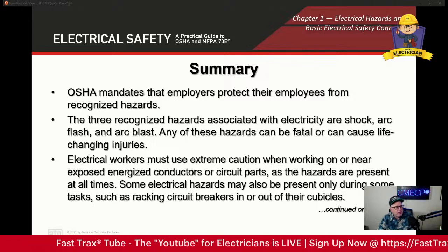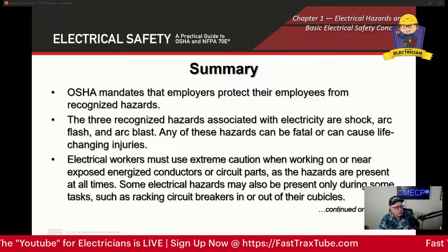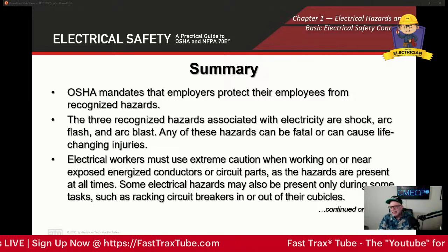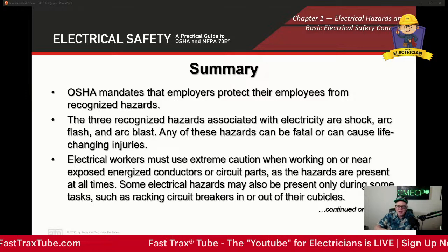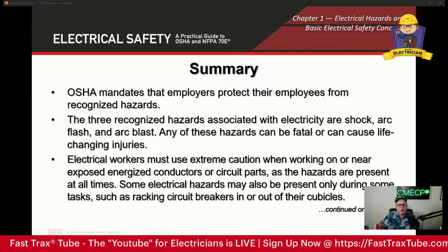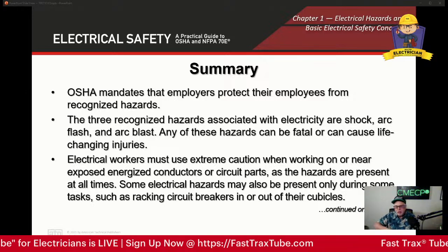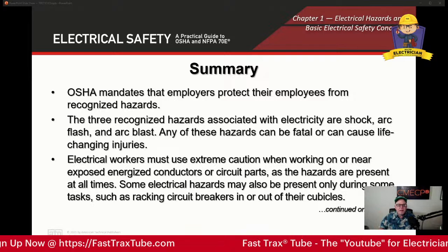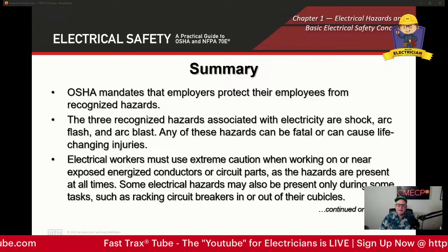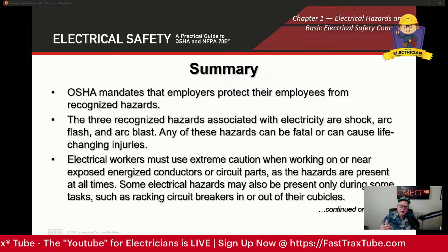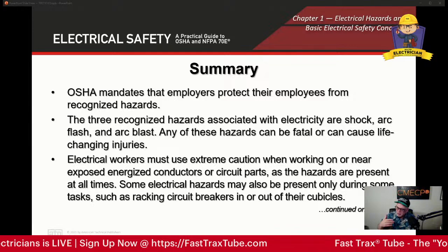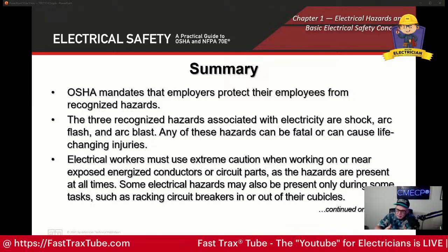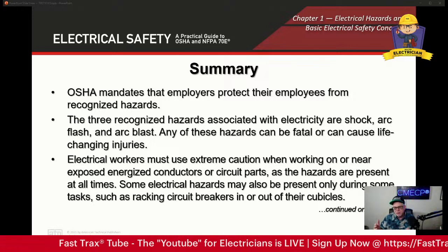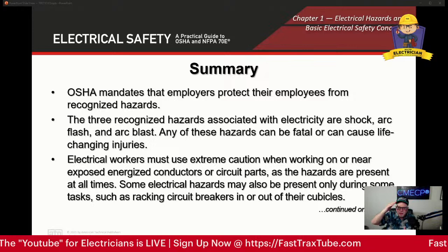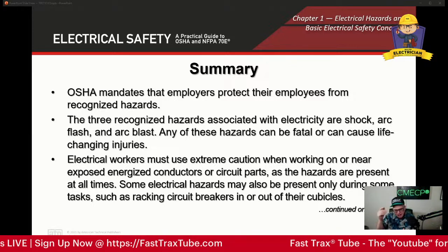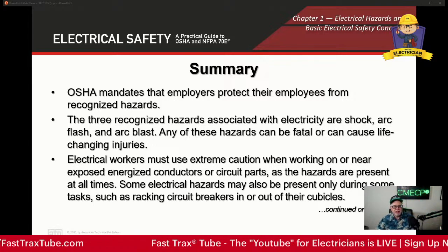Some electrical hazards may also be present only during certain tasks, such as racking circuit breakers in and out of their cubicles. That's true. Even when you're racking, thinking you're outside of the equipment, maybe in a big switchgear room, racking big circuit breakers in or out, cranking them in and out, you definitely need PPE on because it's getting ready to make or break contact. If something's a ticking time bomb waiting in that breaker, something's malfunctioned, and the moment it makes contact, boom, something blows up. Or maybe while cranking it in, some piece of metal in the framework falls down at the last minute. That's exactly how it can happen, and it can be devastating.